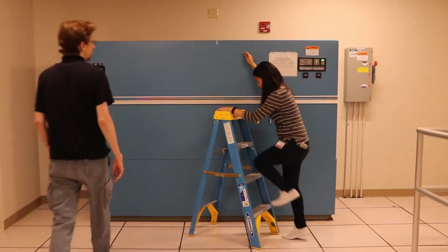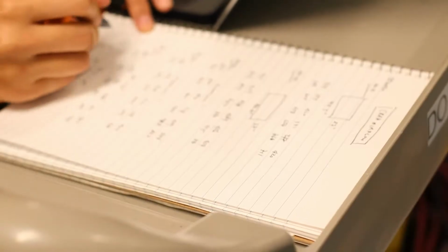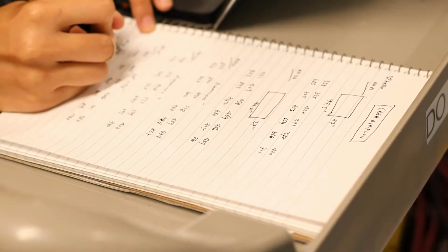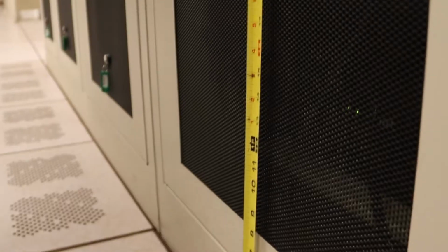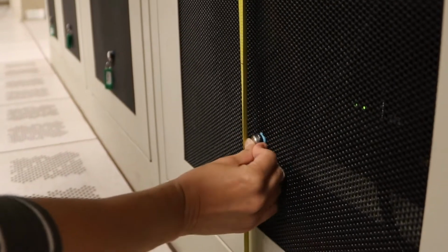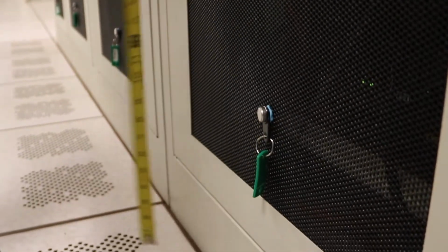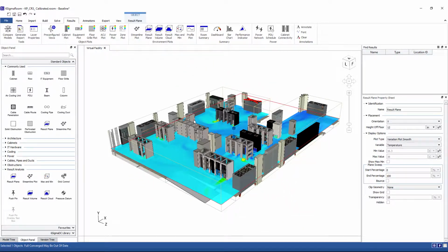These are placed to capture variation in air temperature returning to each unit. Temperature and airflow measurements can reveal the true operational conditions of each CRAC unit. Where necessary, a thermal camera or temperature sensors are used to record the rack inlet temperature over the area of the inlet vents. Finally, the model is solved and all measurements are compared with the simulation.